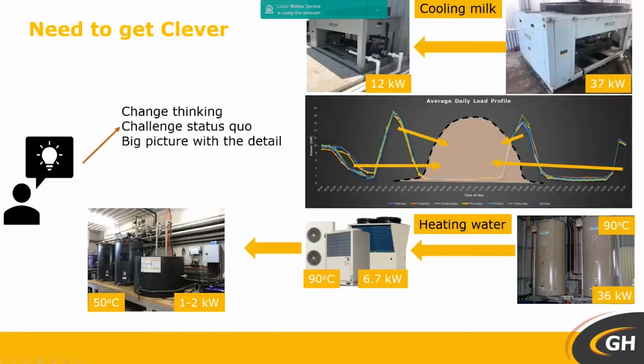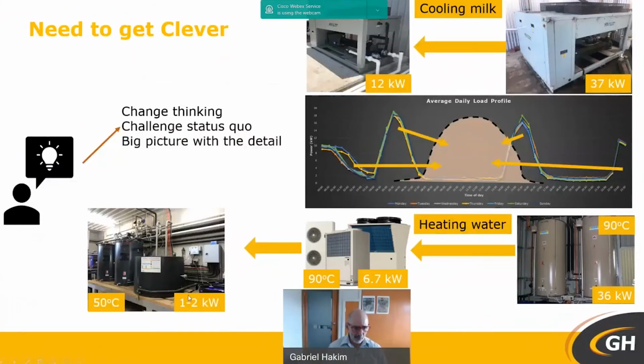Yes, John - for example, on this farm we've got an extra plate cooler, and we're doing this on a new farm where we use it before the milk goes to the traditional plate cooler. We're capturing some heat off the milk into this rinse tank, achieving 32 degrees in the tank. That's one way of capturing heat from the milk, and of course the other way is to put a heat recovery unit on your refrigeration unit.